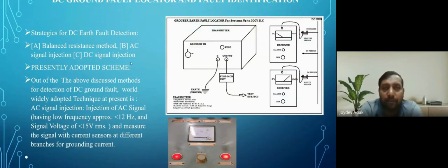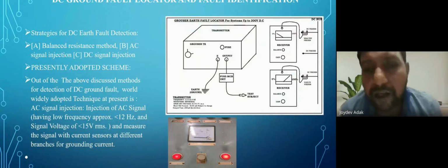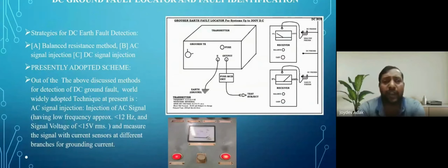And worldwide, presently for online DC fault locators, we are utilizing AC signal injection, where we are injecting a signal of low voltage and low frequency, or a pulse-type signal. This is the make of the device, and the signal is 11 to 12 hertz sinusoidal, 12 hertz, and 8.5 to 9.5 volts RMS.